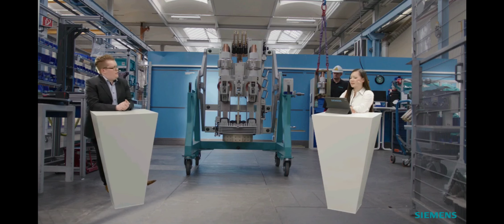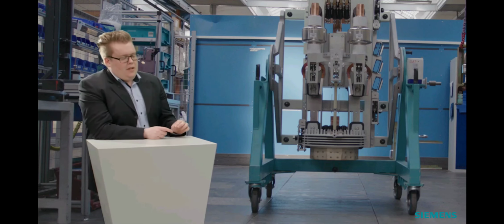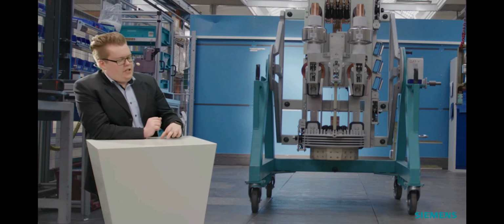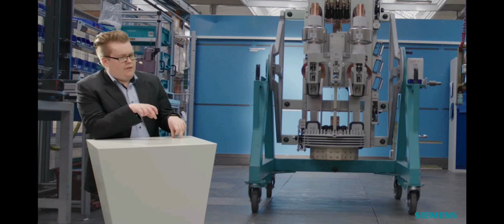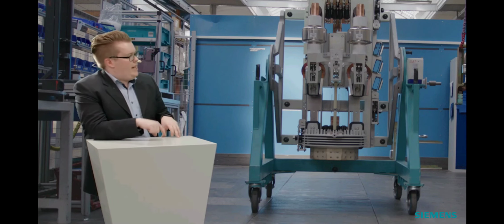All right. Is there any limitation when considering parallel generators? Because I remember that in this dual-logo standard, they mentioned something with the 10 MVA limit. How is it covered here in these parallel generators? I guess I got you. The IEC/IEEE standard only covers a generating voltage above 10 MVA.